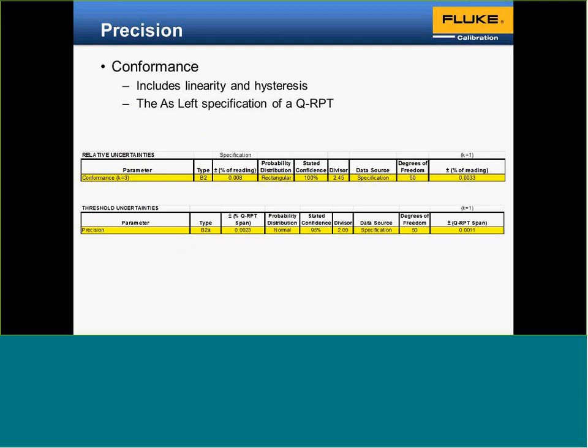For the QRPT, we have a conformance specification of 0.008% of reading down to the threshold, and that's the main specification from the calibration report or our literature. It's reported as a rectangular distribution, so it has a divisor, as with the precision threshold uncertainty. But our goal is to get those to 1 sigma to be normalized.